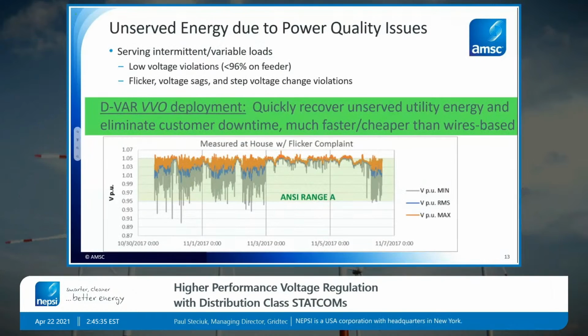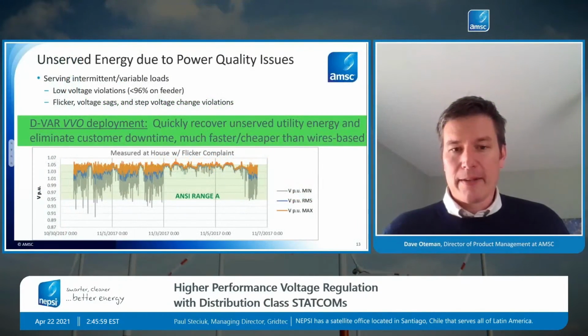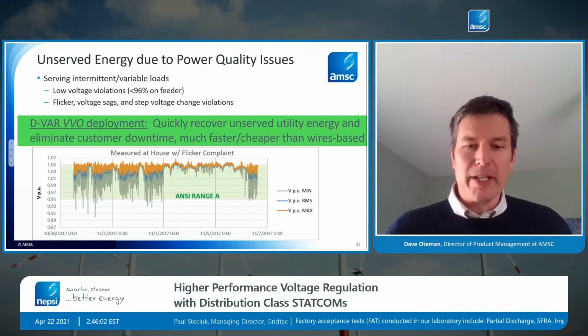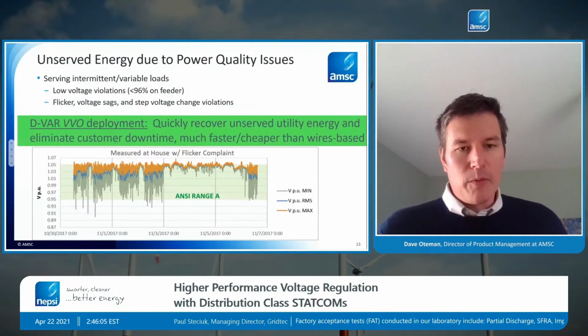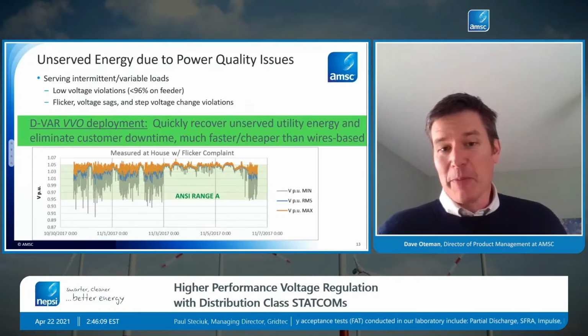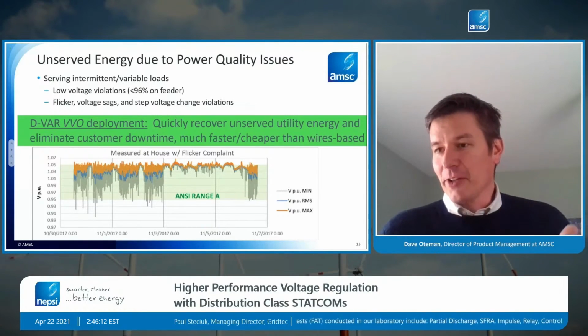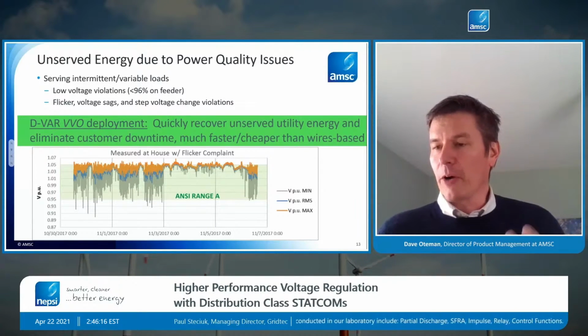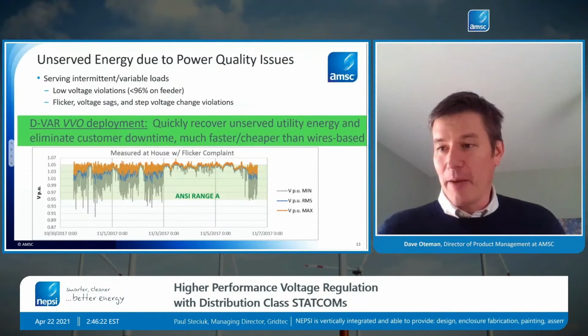The second application we'll cover today is what we call unserved energy due to power quality issues. A lot of utilities serve industrial load, and it's not uncommon for industrial load to create large fluctuating power profiles—crushers, shredders, resistive heating, as I mentioned previously, are loads that can drive significant variability onto feeders. In this scenario there are always three parties involved: the utility, the industrial customer causing the flicker or power quality problem, and other customers, since on the distribution system there are pretty much always other customers.